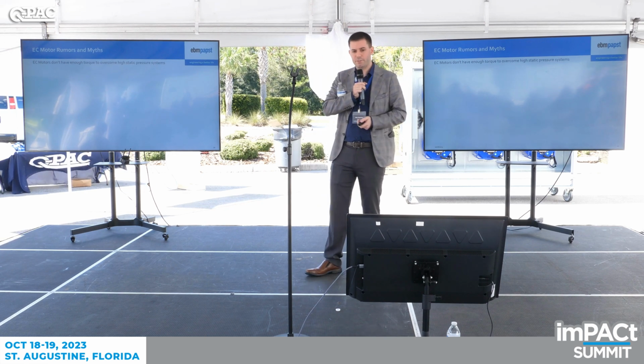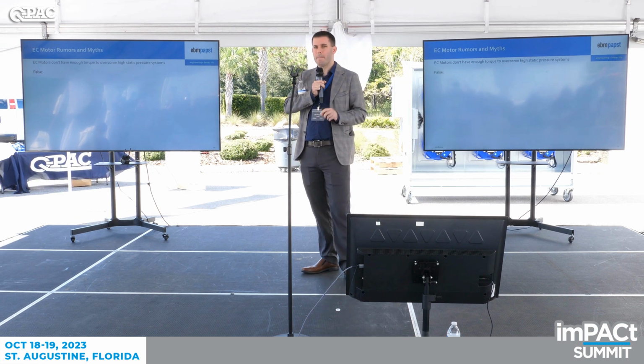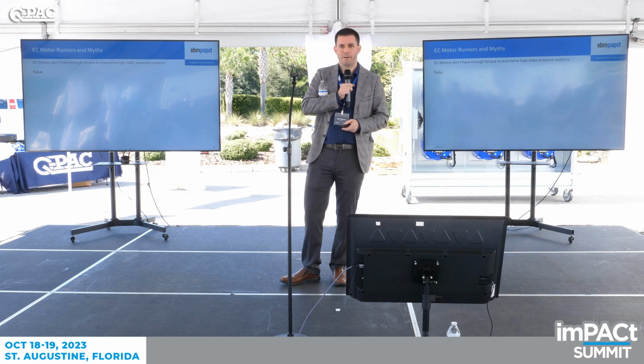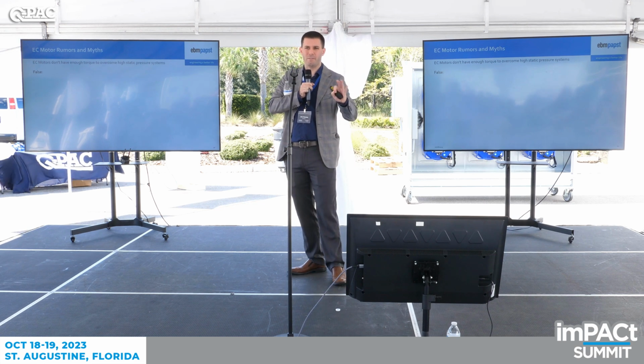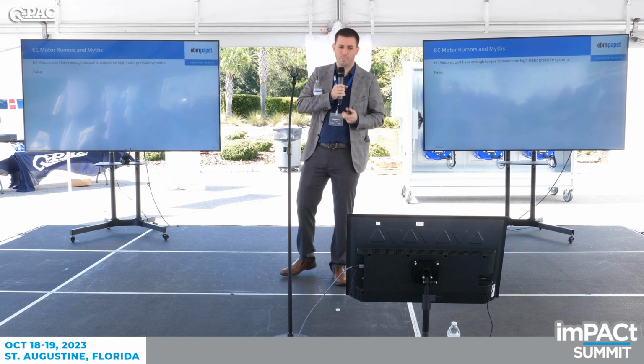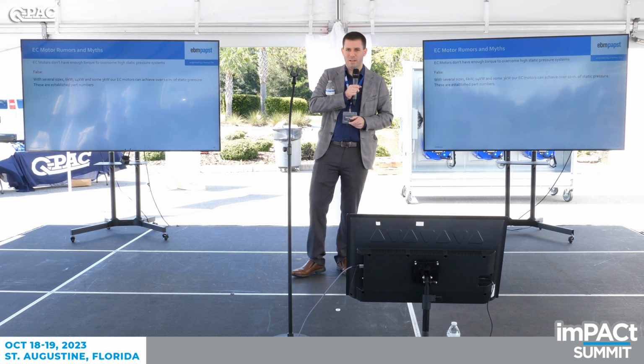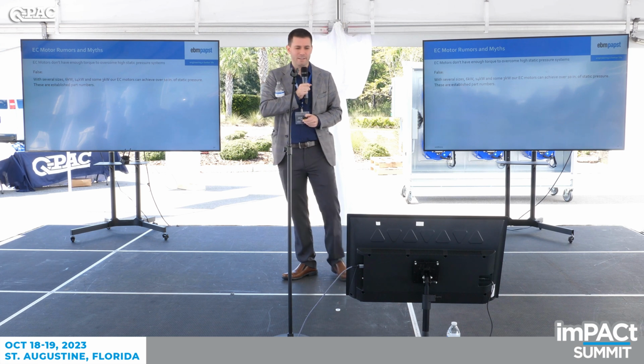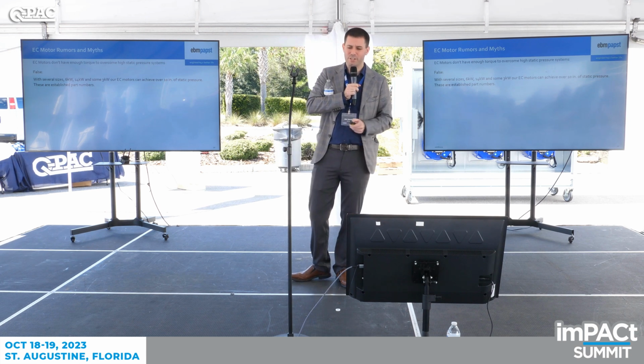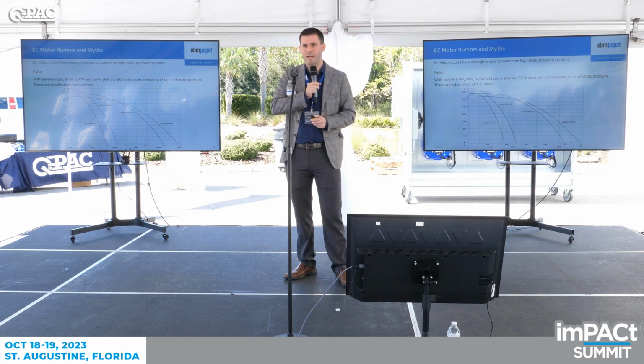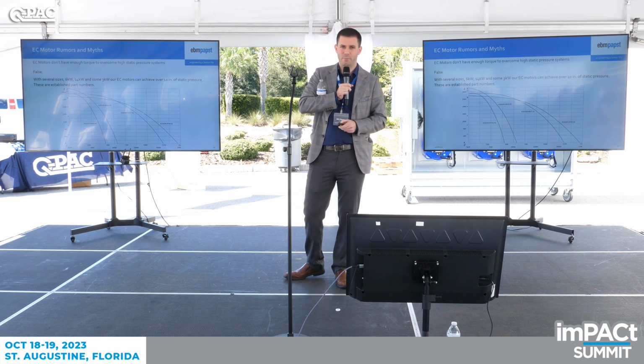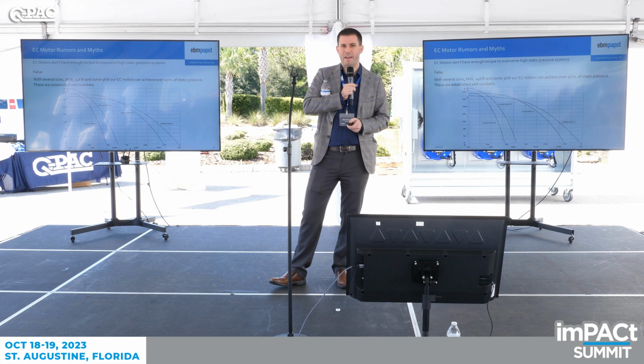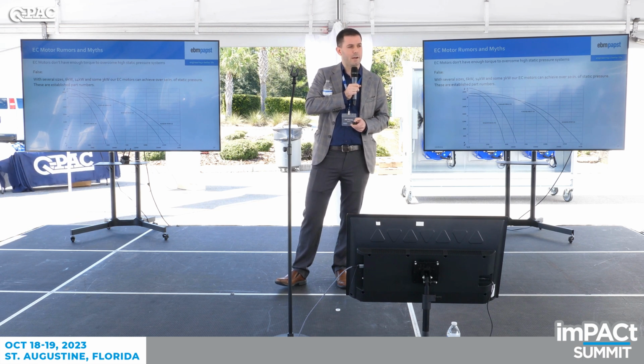EC motors don't have enough torque to overcome high static pressure systems. So this is another one. It's false, but I understand why they said this, because 10 years ago, it's right. EC fans really didn't have high static capabilities. We maxed out probably around 5-6 inches of pressure. That's not the case anymore. So we have kilowatt ranges up to 14 kilowatt, even higher than that in some cases if you have a specialty product, but they can achieve over 10 inches of static pressure now. Fairly reliably, we have a few products that can do it. So high static applications are no longer really a limitation for EC product like it used to be.